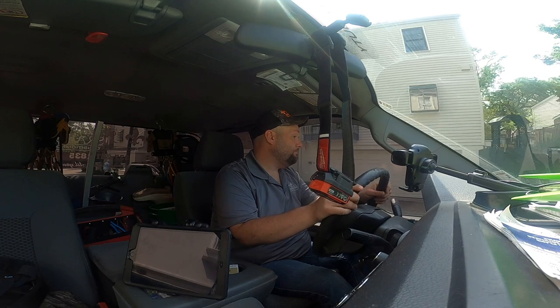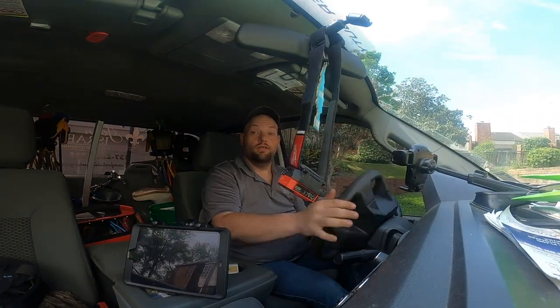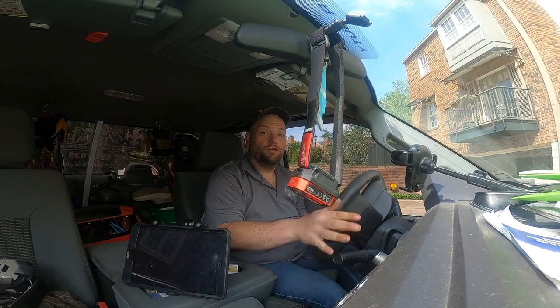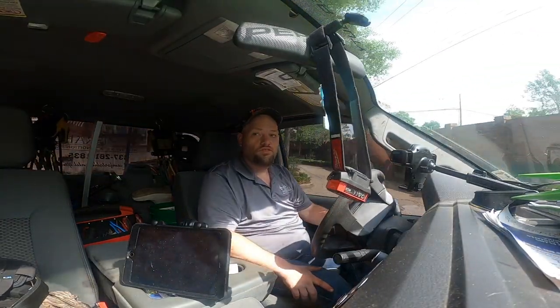Alright guys, I'm pulling away from this call. It's a two-story condo - that was the upstairs system. I didn't find anything wrong with it, and when I went back upstairs it had already dropped three degrees and was cooling very well. They said it was at 80-something yesterday when it was trying to cool. They called me about 8:30 last night - I told them to turn it off and I'd come out this morning. When they did that it reset. I don't know if the compressor was in thermal overload for some reason - I didn't see any reason for it with the refrigerant charge and capacitor both being good.